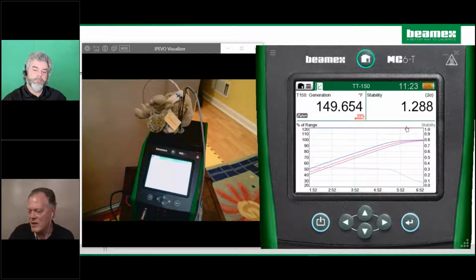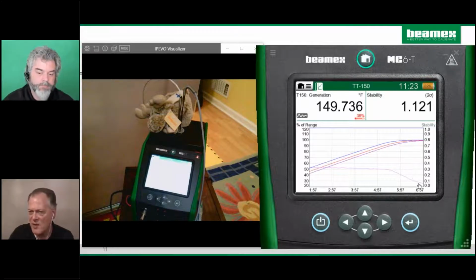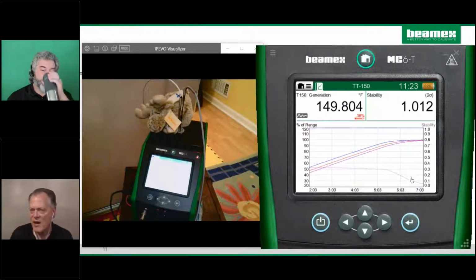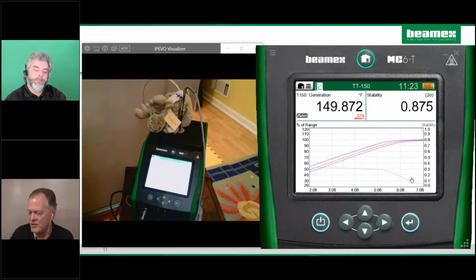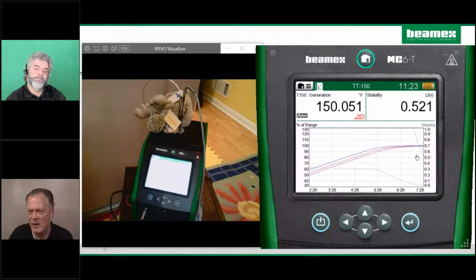As a technician in the field, you want to take your readings when everything's really stable, especially on temperature. So like you say, it adds a level of confidence to the work you're doing, and it's just helping us out here. So there's the stability graph. The small blue line just popped in, and it's fast. It's dropping very quickly here, and pretty soon we should see a red line come in for the reference probe. So these things kind of work in parallel here.